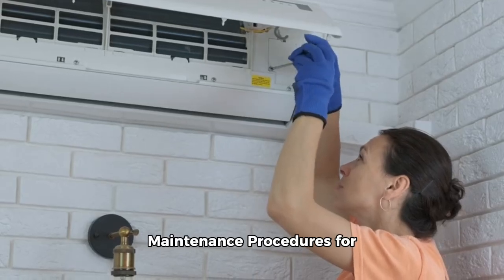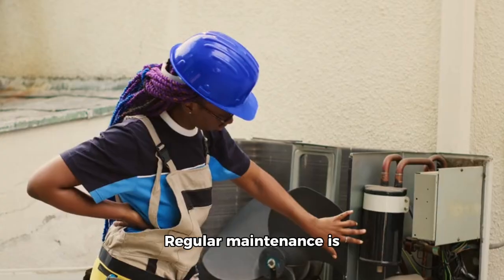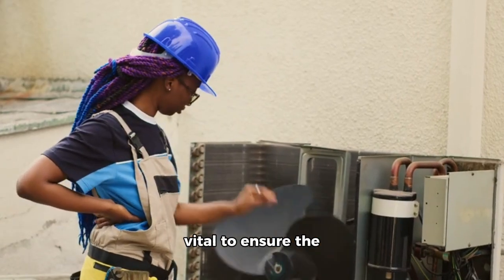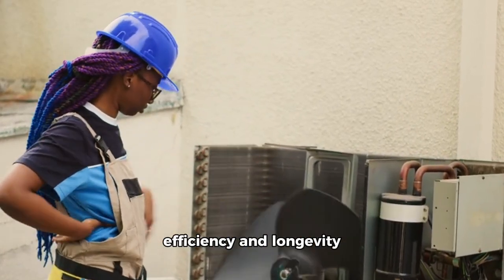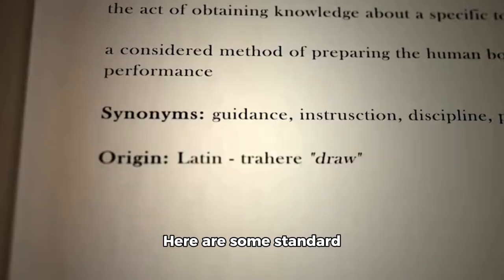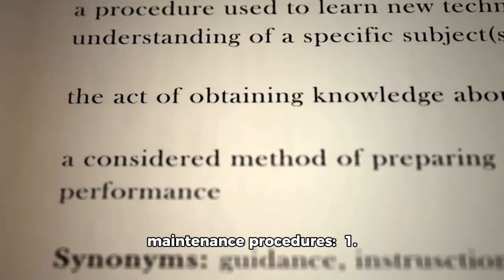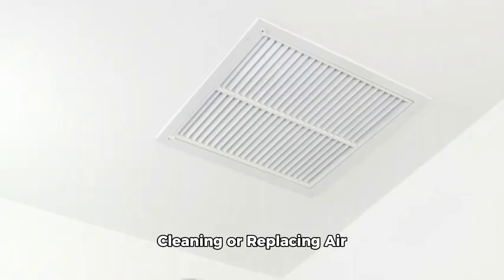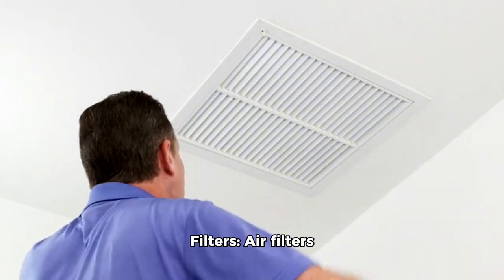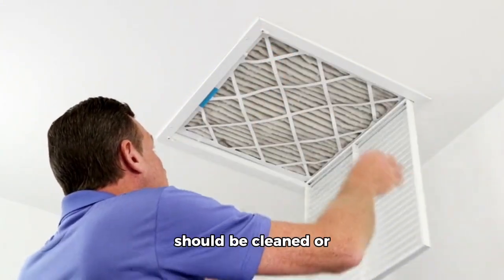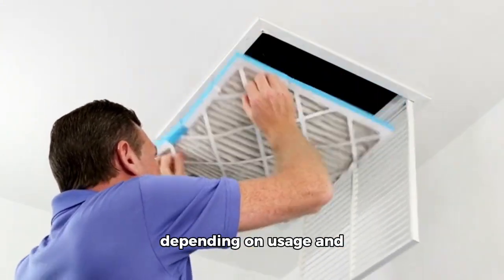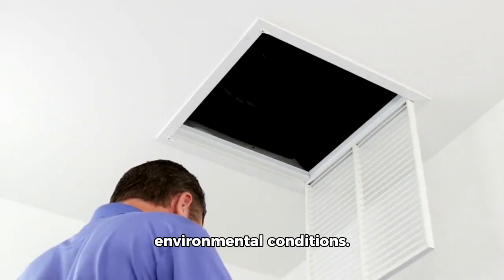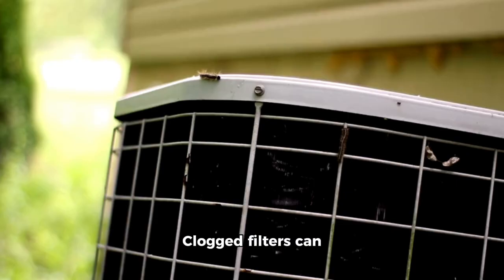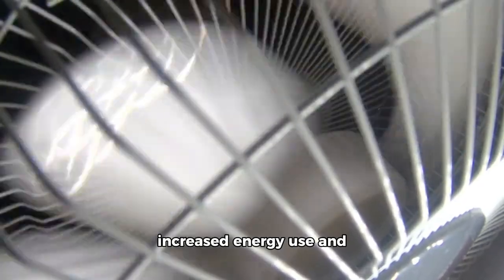Maintenance procedures for air conditioning systems. Regular maintenance is vital to ensure the efficiency and longevity of air conditioning systems. Here are some standard maintenance procedures. 1. Cleaning or replacing air filters. Air filters should be cleaned or replaced every 1 to 3 months, depending on usage and environmental conditions. Clogged filters can reduce airflow and cause the system to work harder, leading to increased energy use and potential damage.